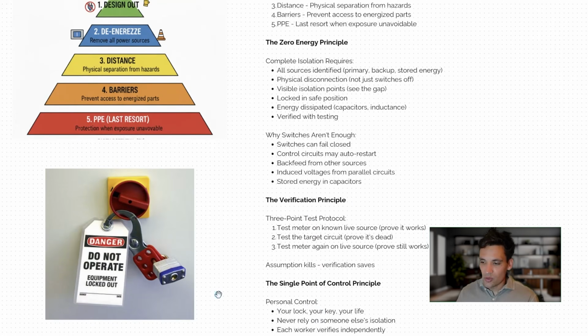Now, behind this all is the lockout tagout procedure. The principle behind this is that the person doing the work is responsible for putting in place the isolations that they're working on. And this is all done through personal isolation locks. The person doing the work looks at the drawings with an isolation officer or someone who's a permit officer, someone who's in charge of doing the work. They agree to all the isolations. They look at all the isolation ports. They look at the drawings. They confirm, yes, it's isolated here. Yes, it's isolated here. Yes, it's isolated here. I'm happy. Then they go through and they put a personal padlock on every single isolation point, and they have the key to that lock.